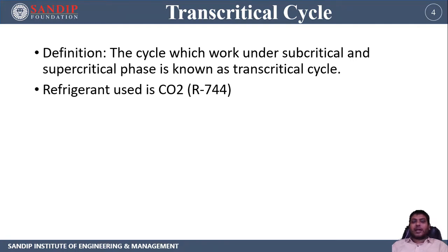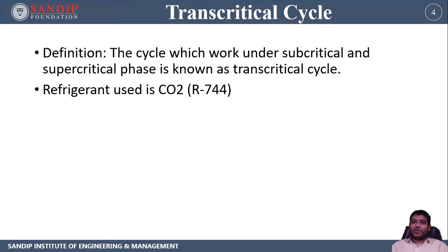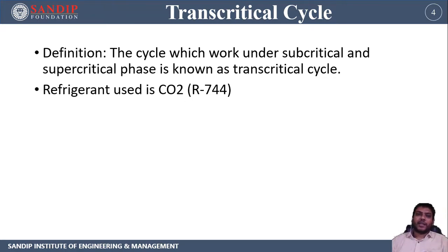The topic is the transcritical cycle. There are two types of cycles: one that works below the critical point, known as the subcritical cycle, and one that works above, known as the supercritical cycle. The cycle which works under both subcritical as well as supercritical phase is known as the transcritical cycle. If a cycle has high pressure above the critical pressure of the working fluid, we call it a transcritical cycle. The refrigerant used is carbon dioxide, with refrigerant number R744.